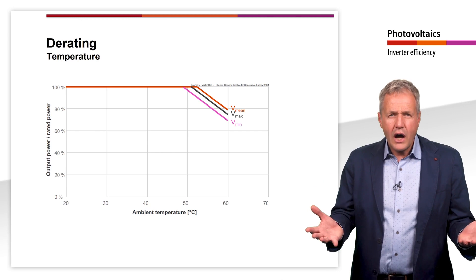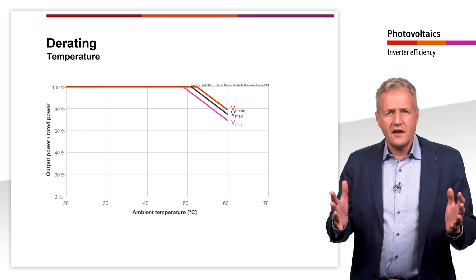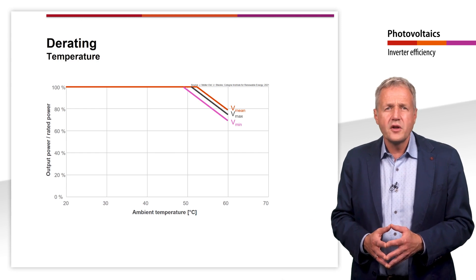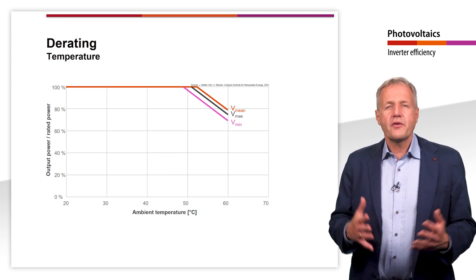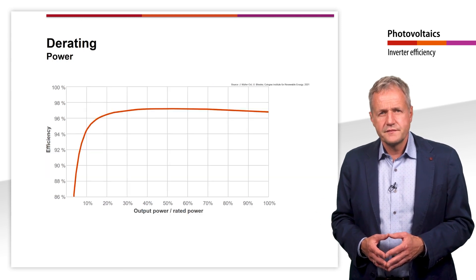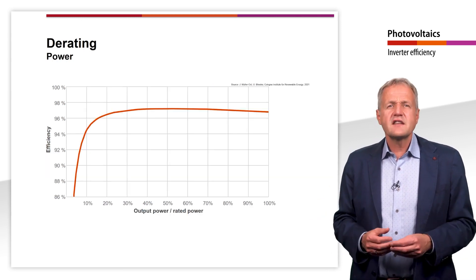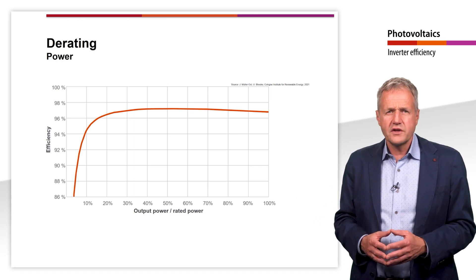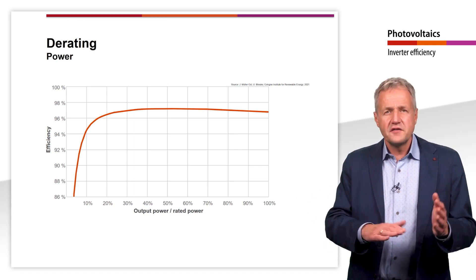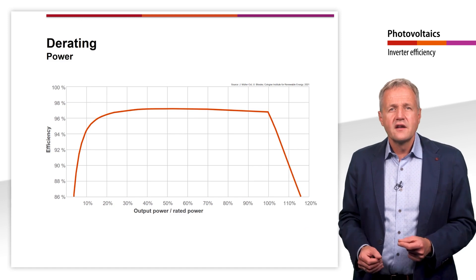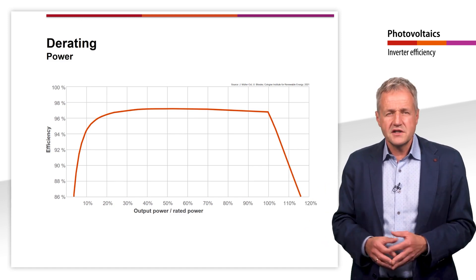Reliable housing cooling and a mounting location that is as evenly cool as possible are therefore important for the operation of an inverter. The inverter's derating is based on the temperature of the components, but it can also be observed in the efficiency curve, provided that the higher power is applied long enough to cause critical heating.